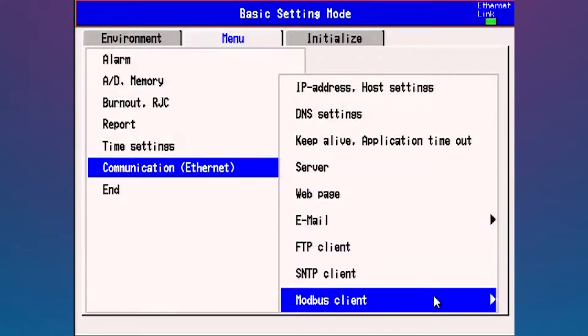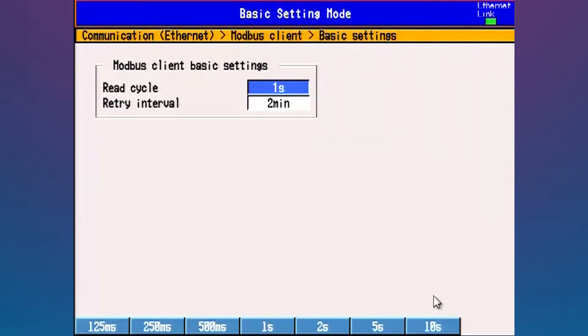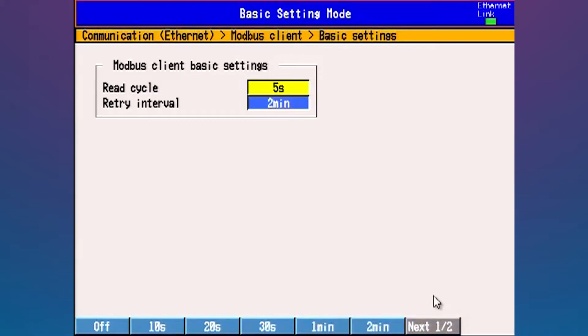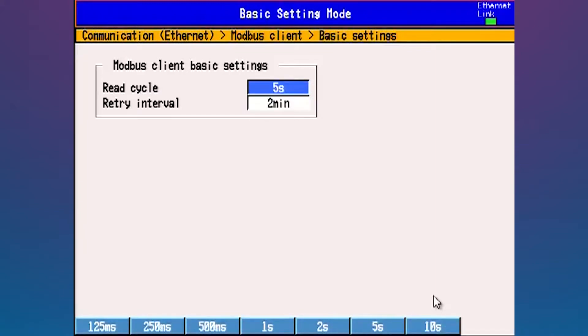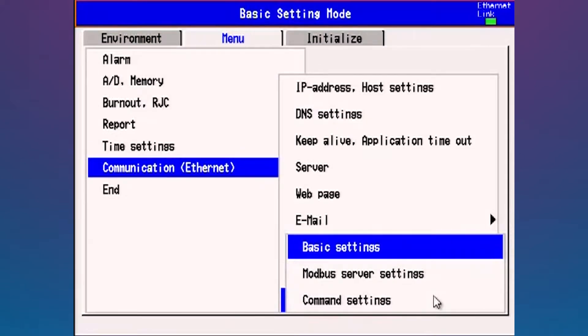Now let's get down to the actual Modbus configuration. It's going to come up with three choices. Pick your basic setting. This is essentially how fast you're going to poll your remote I.O. I recommend no faster than one second. That will usually work on most networks. If you're doing something slower like temperatures and you don't need updates all that fast, you can change this to a different poll rate. You can change it by accessing the function keys. Since I've made a change, see how it's in yellow? Hit the display enter to accept that change.